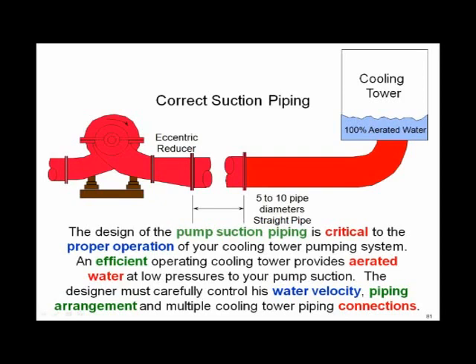So for suction pipe on a tower, you want your eccentric fittings on the top of the pipe, flat on top. You want your reducers on the bottom. You want to keep it as straight as you can, and we want straight pipe running into it, velocities down. And a rule of thumb we give everybody is to keep the pressure drop between the tower and the suction flange to 5 feet. Now you can do what you want to, but it's kind of a rule of thumb. But remember, any pressure drop on that water, you're going to get air out. That's the thing you need to remember.